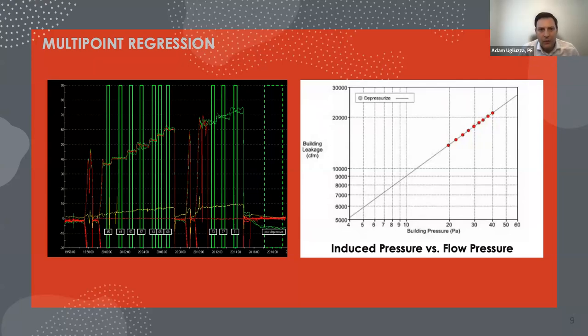I guess it depends on how you're naturally ventilating. If you're naturally ventilating through random holes, I would not recommend doing that. Meaning you're just leaving it up to the contractor to not create continuity with the air barrier or an interface. You don't really know how well you're ventilating in that case. If natural ventilating is through operable windows or relief dampers or something along those lines, I still would prefer not to do that. I think you'd still be losing energy. You'd be addressing the ventilation requirement, but there are other ways to ventilate, with energy recovery systems or heat recovery systems that allow you to get that air exchange, but under a controlled method that is more energy efficient, but achieves the same thing.